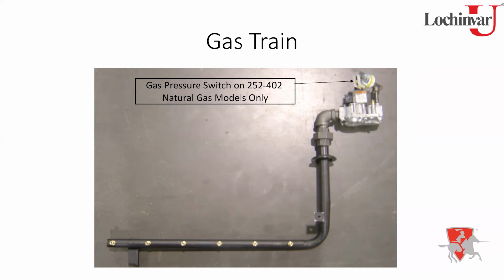Two things I do like to point out when we're looking at this picture. Number one, Charles mentioned the orifices down here. It's not a bad idea just to make sure those are clear of any dirt or debris or trash or anything when you do your annual, because you're going to have to take this inlet gas manifold out anyway, so it doesn't hurt. Also, another thing, follow along with me. This gasket, a lot of people call it a donut gasket, but the professional name is escutcheon gasket. And do not ask me to spell that because I will butcher it. So that is what's sealing the inlet gas manifold where it penetrates through the top of the combustion chamber and goes down to your burners. That's what's sealing the air chamber down there.